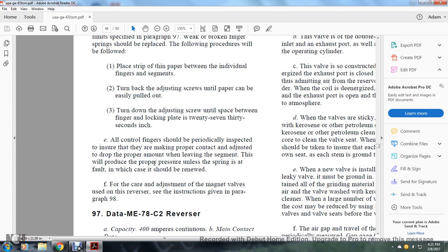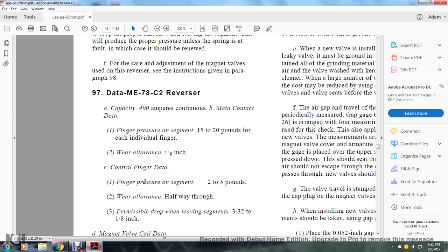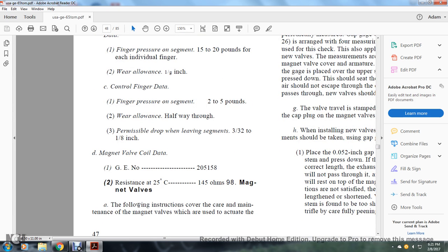For care of the adjusting of the magnet valve and use of the reversor, refer to paragraph 98. Data for the ME78C2 reversor: capacity 400 amperes continuous on the main contact. Finger pressure on the segment: 15 to 20 pounds for each individual finger. Wearing allowance: 1/8 of an inch. The control finger data: finger pressure on the segment of 2 to 5 pounds. Wearing allowance: halfway through permissible drop, leaving the segment 3/32 of an inch. Magnet valve coil, GE number 205158, resistance at 25 degrees Celsius: 145 ohms.